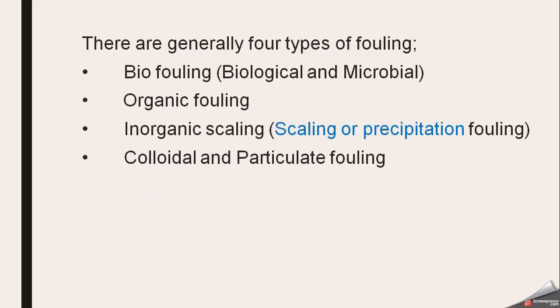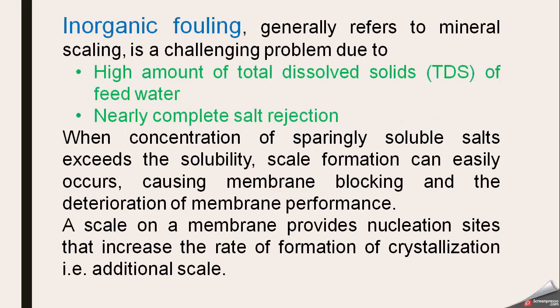Before that, we already described in our previous video that there are generally four types of fouling: biofouling, organic fouling, inorganic scaling or precipitation fouling, and colloidal and particulate fouling. Here we are focusing on inorganic fouling, basically inorganic scaling. Inorganic scaling generally refers to mineral scaling, and this is a challenging problem due to, number one, the high amount of total dissolved solids of the feed water and nearly complete salt rejection.